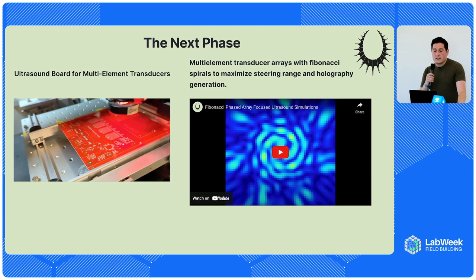On the right, you're seeing a production of our ultrasound boards. This is a design we built off of an open source design from a firm called Open Water. This board has 128 channels, or 128 elements. Think about what an element is: an ultrasound transducer is a piece of piezoelectric material. When you run electrical current through that piezoelectric material, it oscillates, creating the ultrasonic wave.